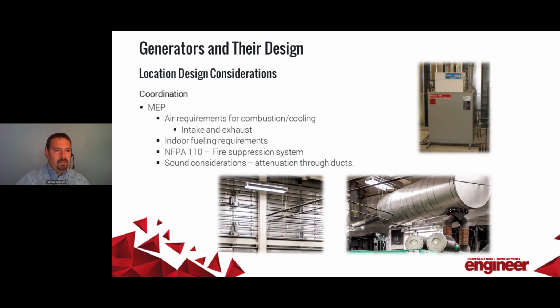And as it relates to mechanical design, you need to coordinate with your mechanical counterpart for air intake, for combustion and cooling, and also for exhaust. You're going to have some kind of a muffler on the generator that's above the generator. So there's requirements for the exhaust off of that. Are you taking the stack all the way up through the building and out through the roof? Where is that exhaust going? How many floors is it?